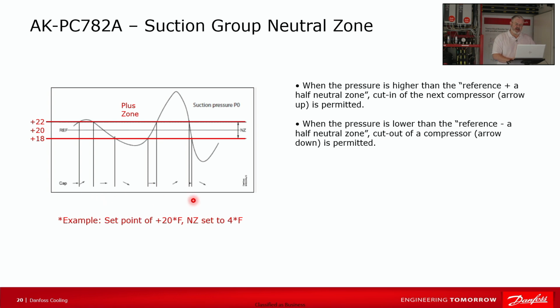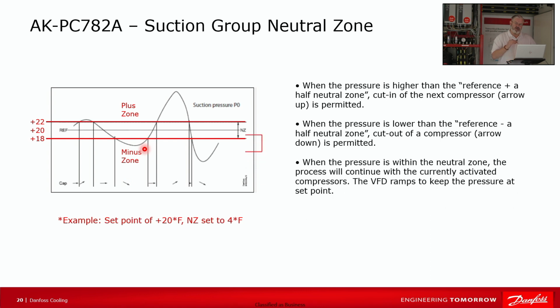The opposite side of that would be what we call the minus zone. Once we turn that compressor on, it's a little too much. We've ramped down the inverter. The pressure's still falling. We get to this point, we enter the minus zone, and now it's time to turn the stage off. And then it'll float back up. When you're not turning something on or off, that's when you're actually within the neutral zone, which means you're no more than 2 degrees higher or 2 degrees lower than the set point that you define. And when you're in the neutral zone, you use the VFD to maintain capacity. So you ramp that between 30 and 60 hertz to keep you at temperature.